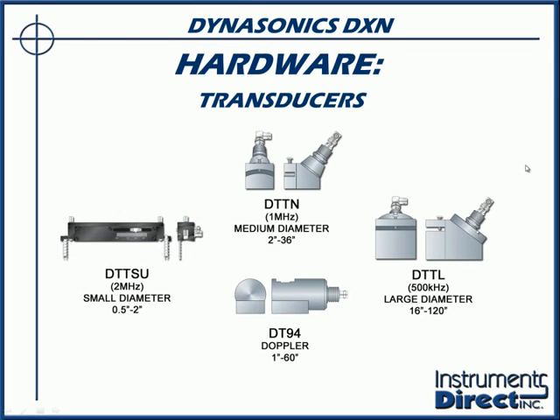For bigger applications or heavier solids applications, again using transit time technology, to the right is the DTTL, which is a 1/2 megahertz transducer, and we use this traditionally with very large water-like applications. Need to go over to the Doppler mode? Well, the picture on the bottom is the transducer, the DT94. It's the traditional Doppler transducer that starts at 1 inch and goes up.